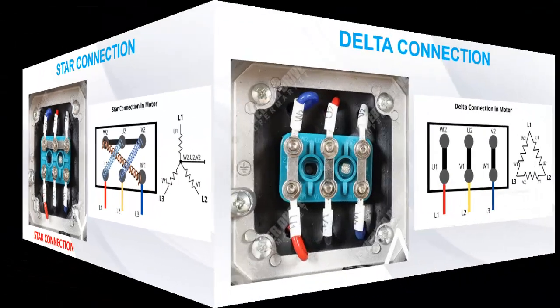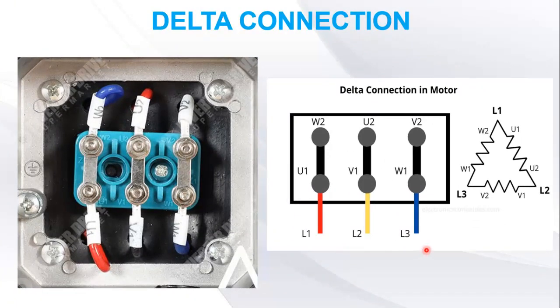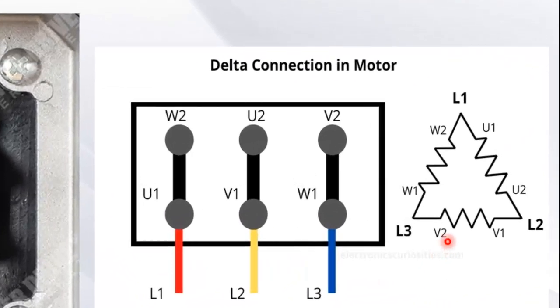Now let's see how motor can be connected in delta configuration. In this drawing, again three sets of windings are connected in delta, in which one end of one winding is connected to one end of second winding. Remember, always connect W2 with U1, U2 with V1, V2 with W1.